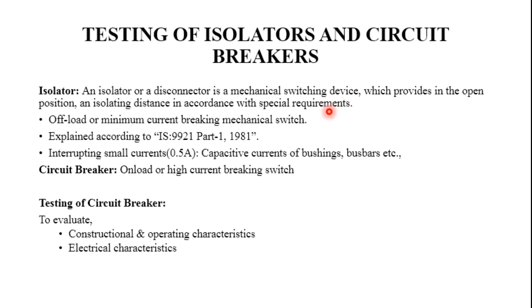The isolator or disconnector is a mechanical switching device which provides, in the open position, an isolating distance in accordance with special requirements. It is capable of opening as well as closing the circuit when either a negligible current is broken or made, or when there is no significant change in the voltage across the terminals of each pole of the isolator.